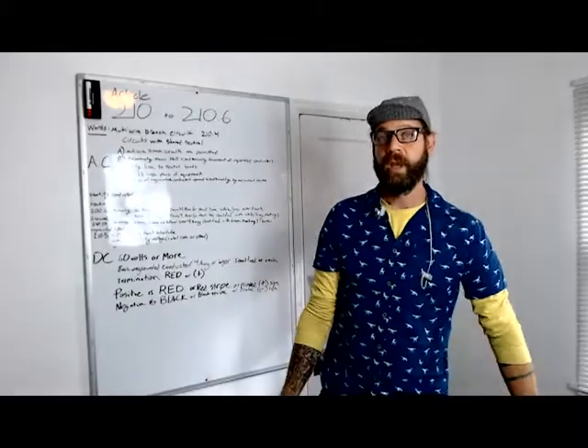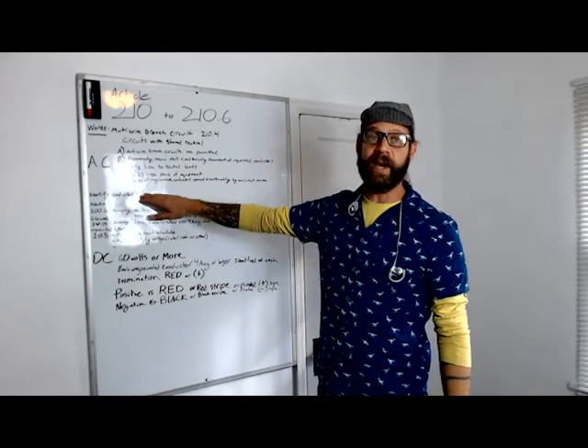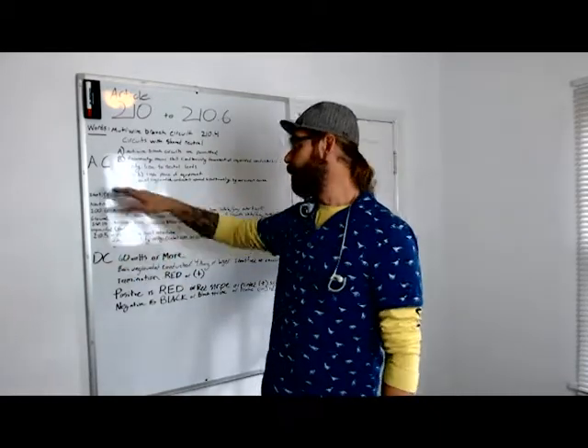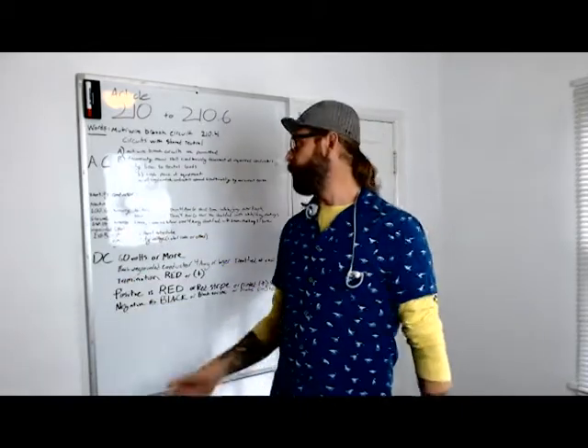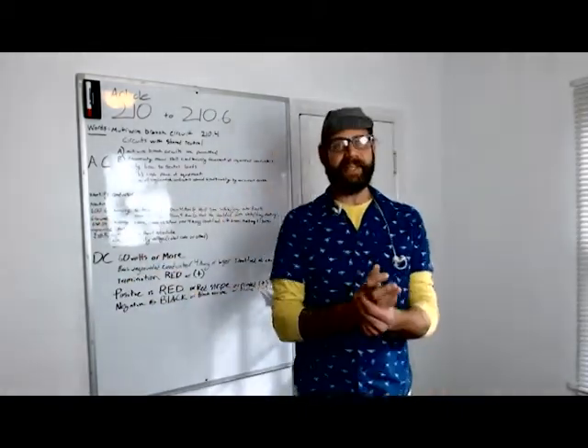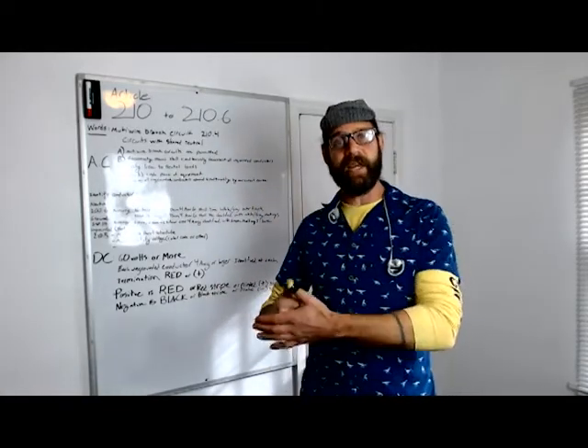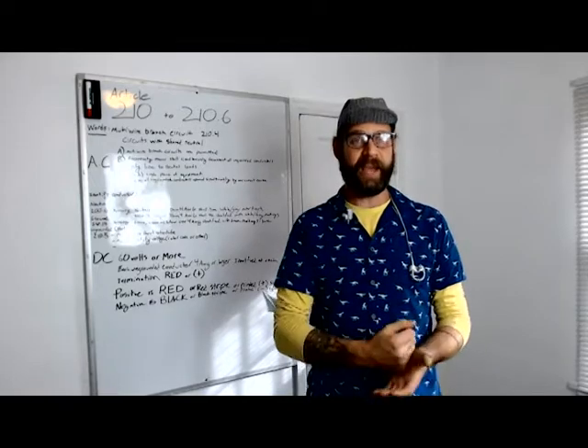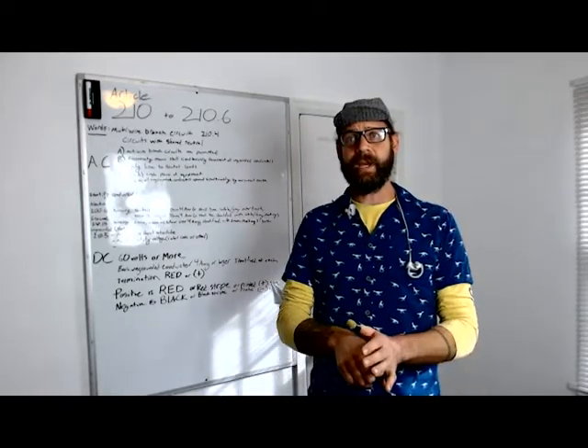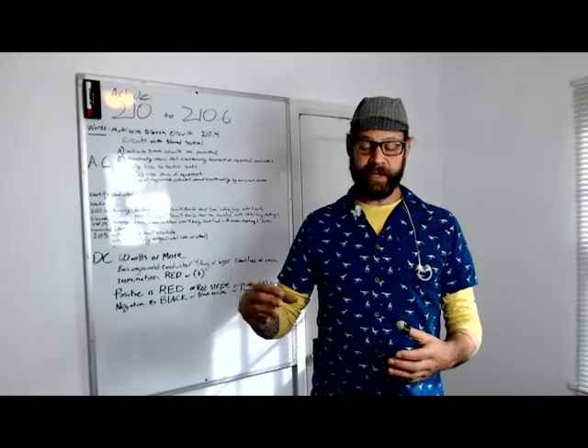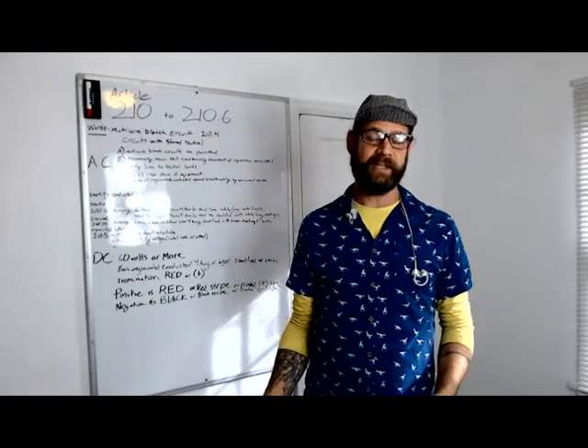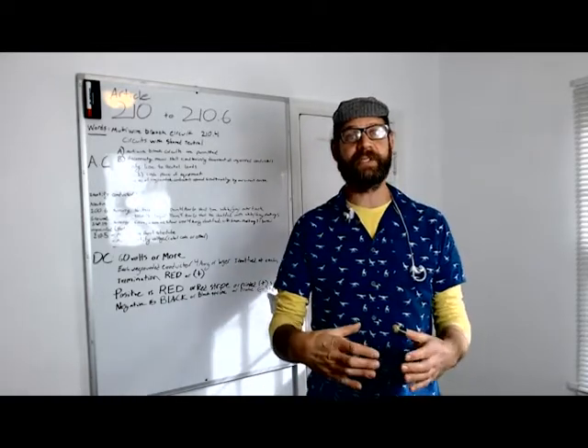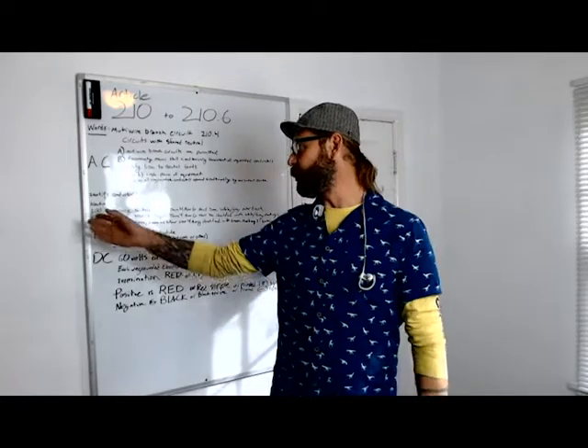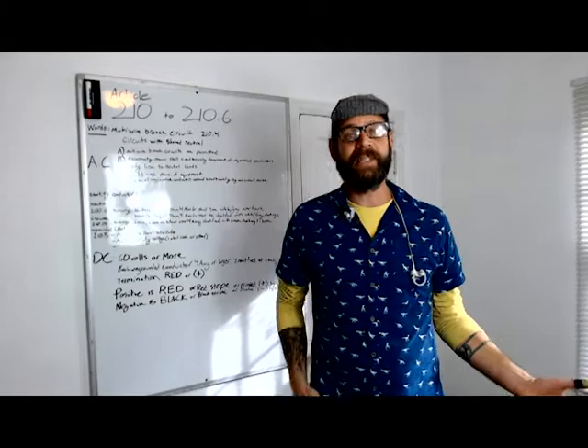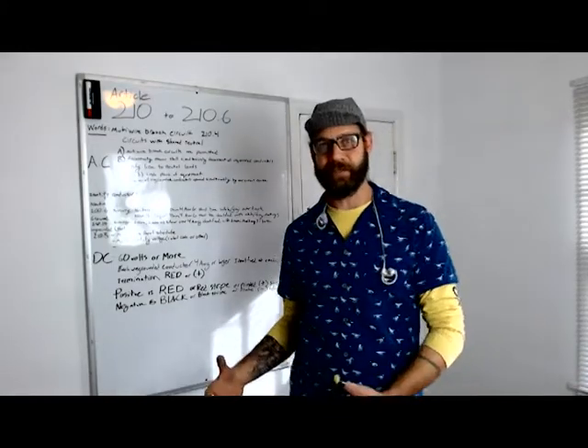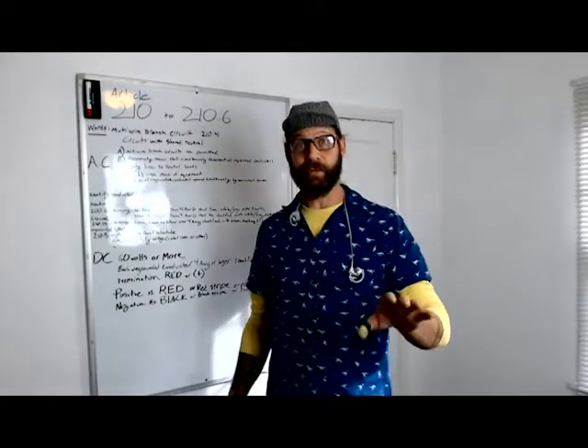All right, so the code goes on to require that you identify conductors, and it essentially says the grounded conductor, the neutral, and it refers to another code section, 200.6. And they're real consistent. If your conductor is under 4 AWG, it's going to have the neutral finish. It's going to be gray or white. And if it's over 4 AWG, it's going to be identified at every one of its terminations or splices as gray or white. The code's real consistent, so this code section doesn't list those things. It just refers you to code section 200.6, where it tells you how to identify grounded conductors. Grounded conductors are neutral conductors.